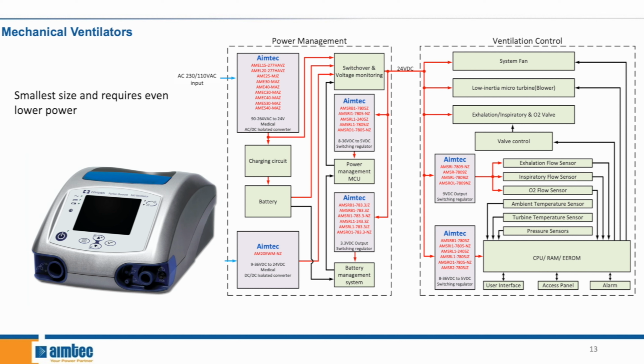Now, for mechanical ventilators, which are actually the smallest size and therefore require even lower power. And again, Aimtec's medical-grade DC-DC converters, the AM20 EWM with a 4-to-1 input voltage range, is built into the device to enable a flexible external DC power source. The input power is converted to 24 volts and powers the valve, blower, and system fan. Switching regulators, which are again non-isolated DC-DC converters, can be used to convert the 24 volts to 9 volts and 5 volts to power the sensors and the microcontroller units.